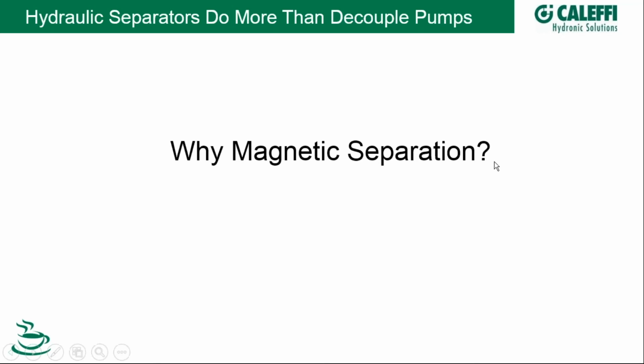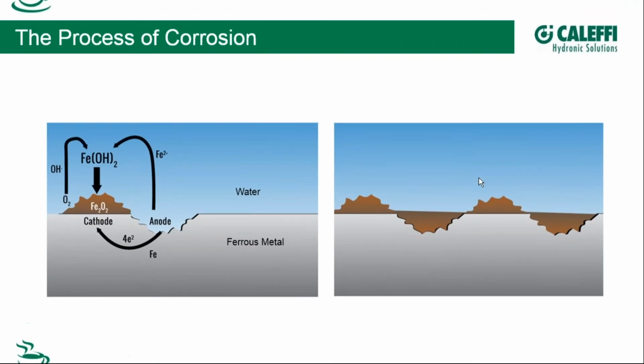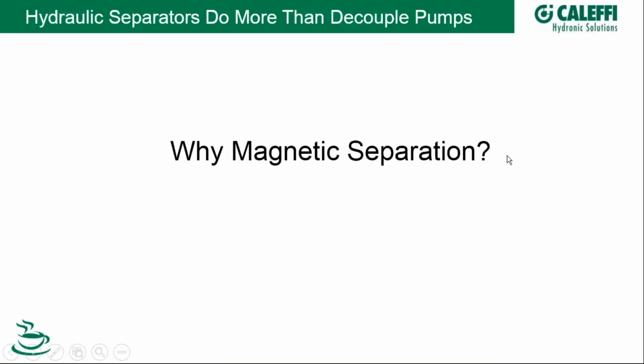Now, magnetic separation is, here in North America, fairly new, but it's been around in Europe for quite some time. And why do we even worry about it if it's fairly new? I mean, it's not an issue, right? Well, let's get into magnetic separation. Where magnetic separation plays a role is in the debris in a system that happens as a result of the aging process. Basically, the system beginning to experience some corrosion. All systems will experience some corrosion. Any hydronic system will experience some corrosion. And the most notable metal to be worried about is ferrous metals.